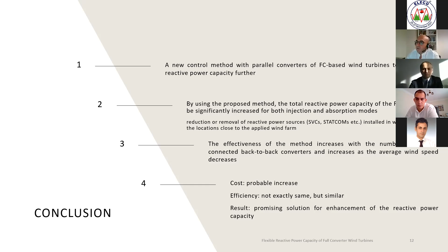As a practical application for the increased reactive power capacity of the turbines, dynamic reactive power allocation of wind turbines in wind farms can be a typical application in order to reduce overall losses. In addition, we can benefit from this method as an additional harmonic filter where the parallel converters are in action.